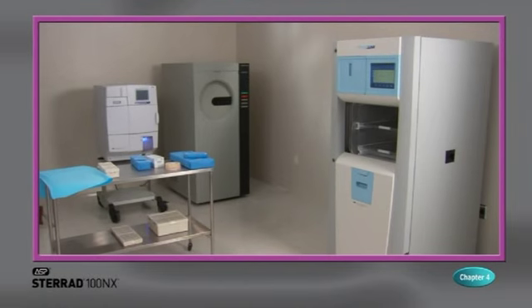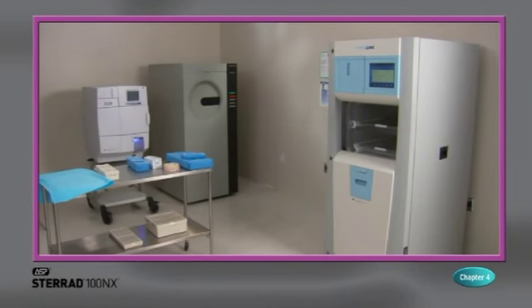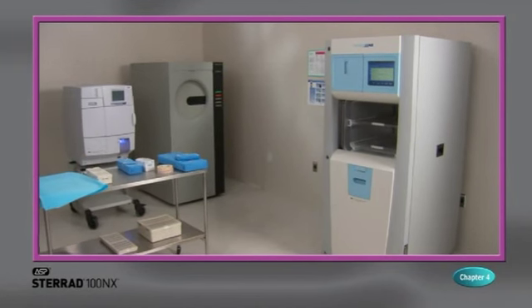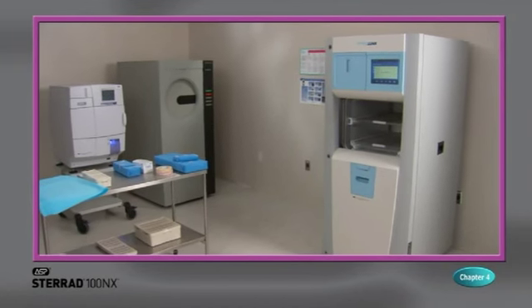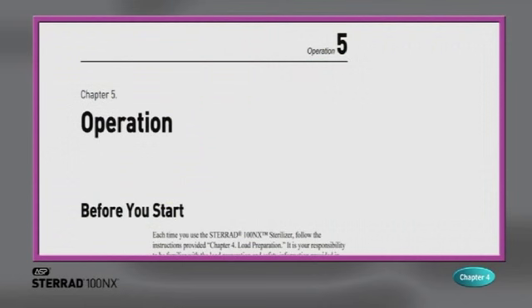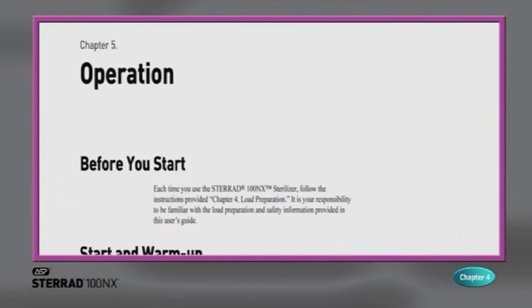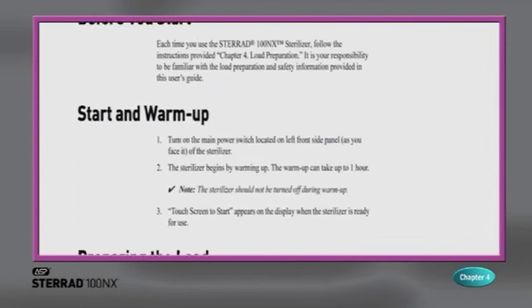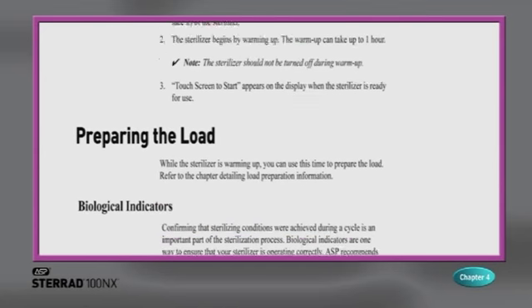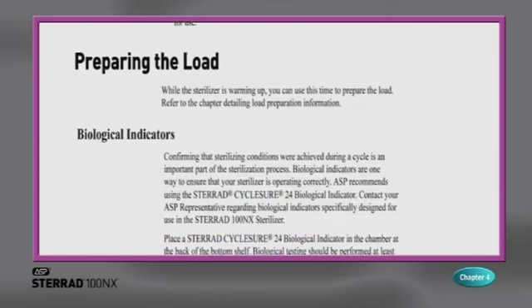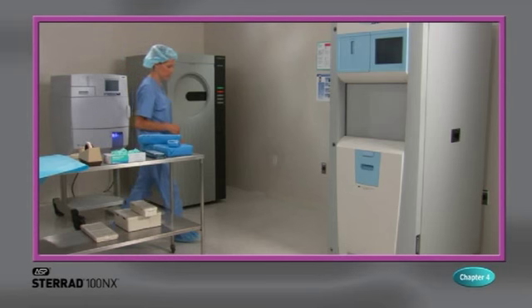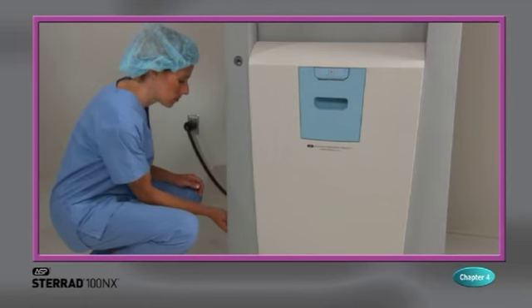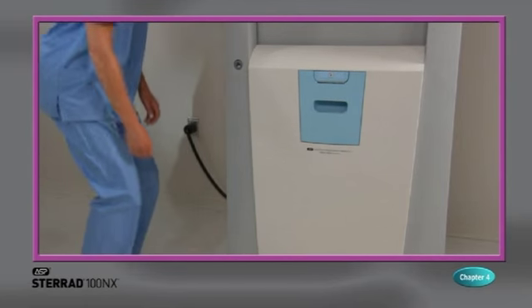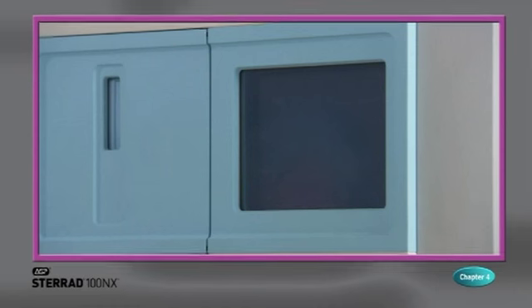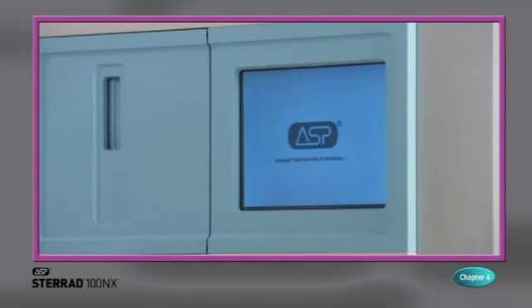Each time you use the Sterrad 100NX sterilizer, follow the instructions provided in Chapter 3 of this DVD regarding load preparation, or refer to your user's guide. It is your responsibility to be familiar with the load preparation and safety information provided in the user's guide. Turn on the main power switch located on the left front side panel of the sterilizer. The sterilizer begins by warming up. The warm-up can take up to 1 hour.